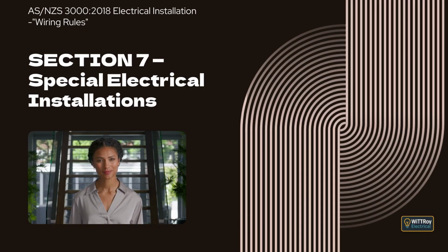Clause 7.9.3.1 Facilities for other than Mode 1 charging. This clause explains that new domestic electrical installations with an enclosed garage or similar space intended to accommodate a motor vehicle must include a facility to enable electric vehicle charging, using approved charging modes. Clause 7.9.3.2 Facilities for Mode 2 charging. This clause explains that Mode 2 charging facilities must meet requirements for minimum circuit capacity, dedicated final subcircuits, compliant socket outlets, minimum installation height, and appropriate switching and protection.